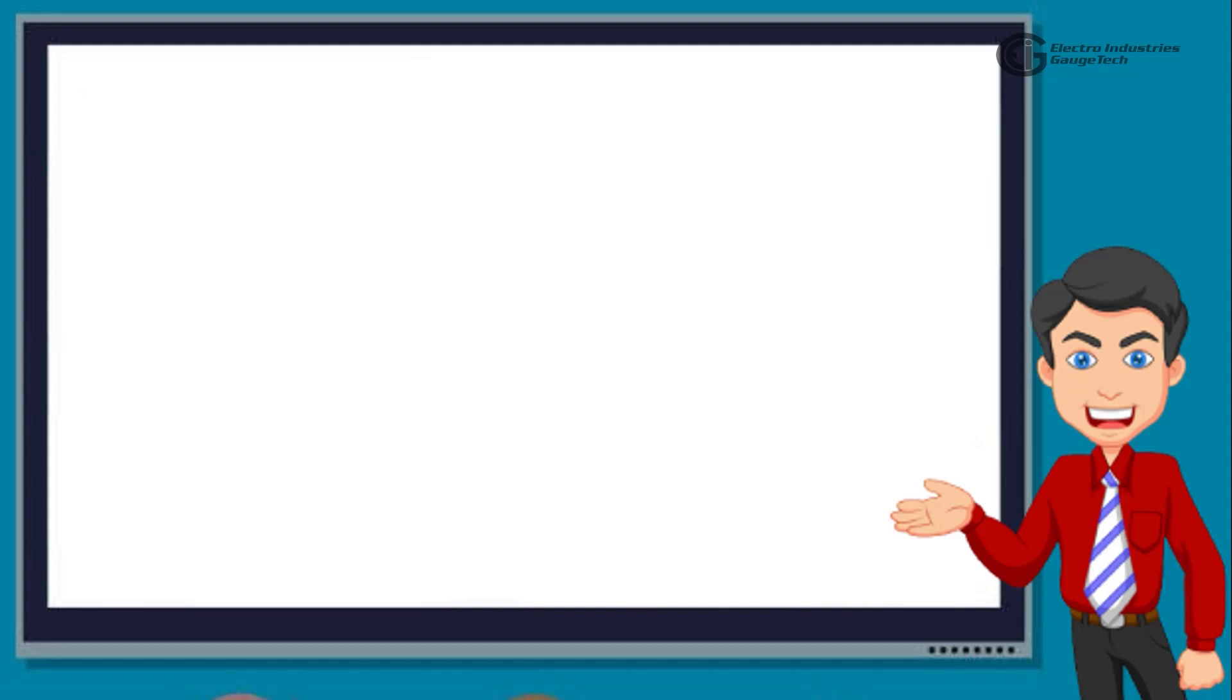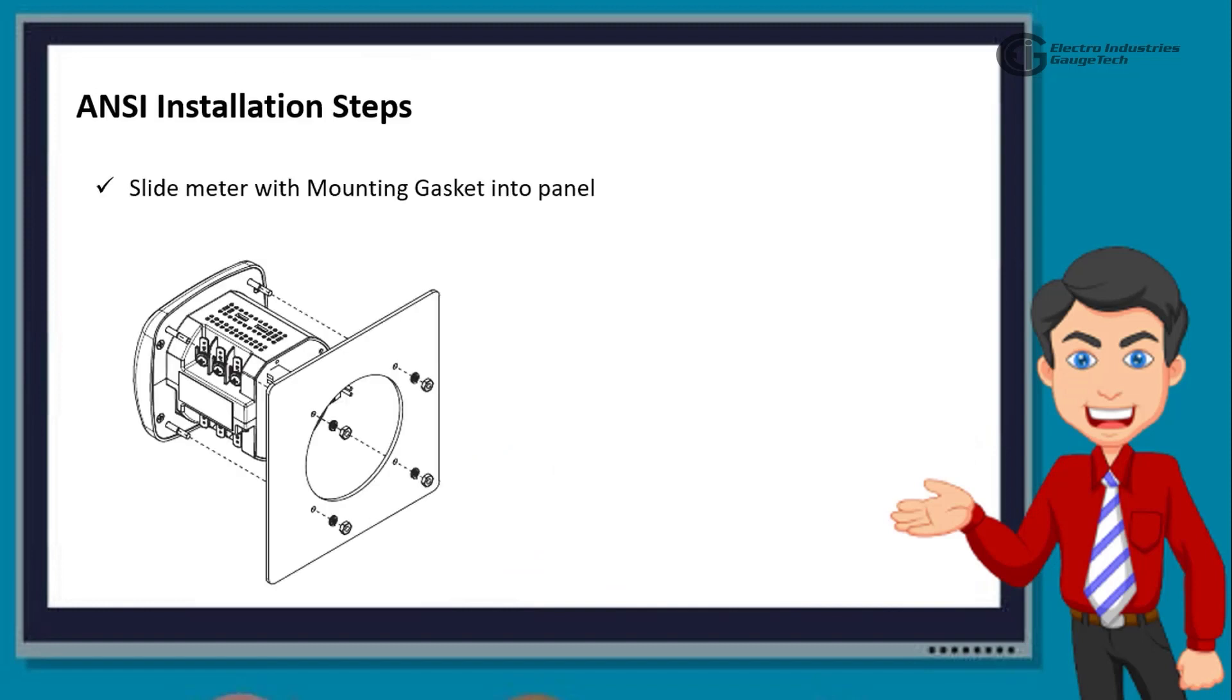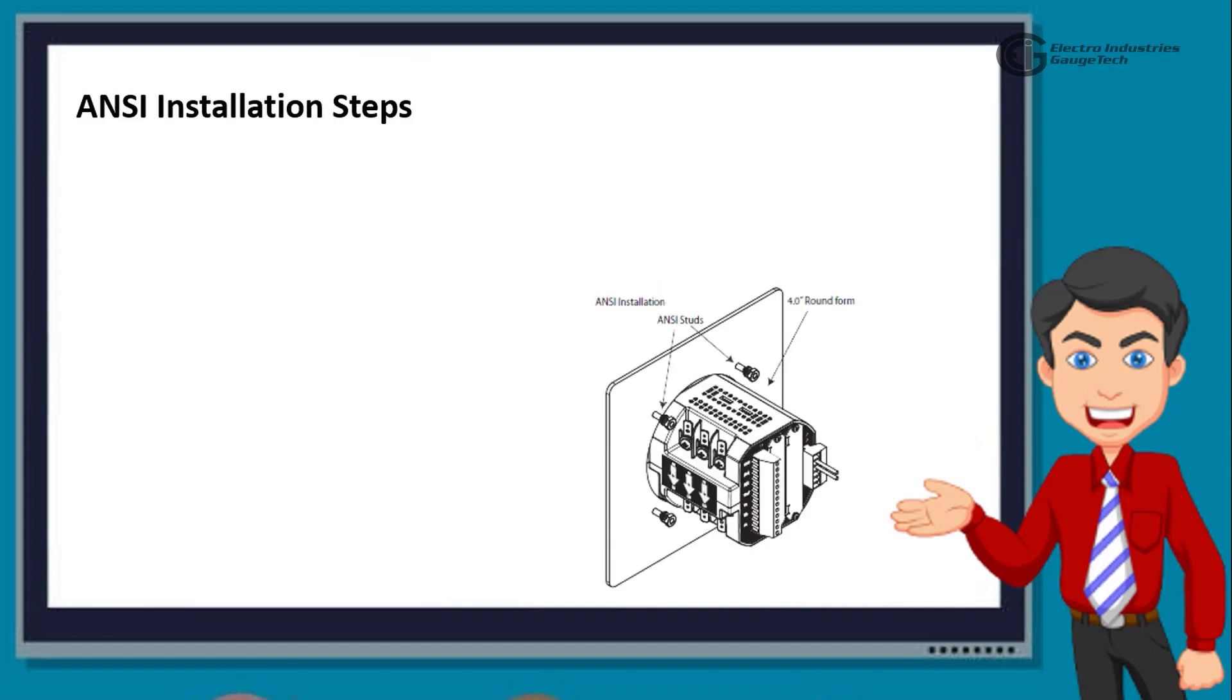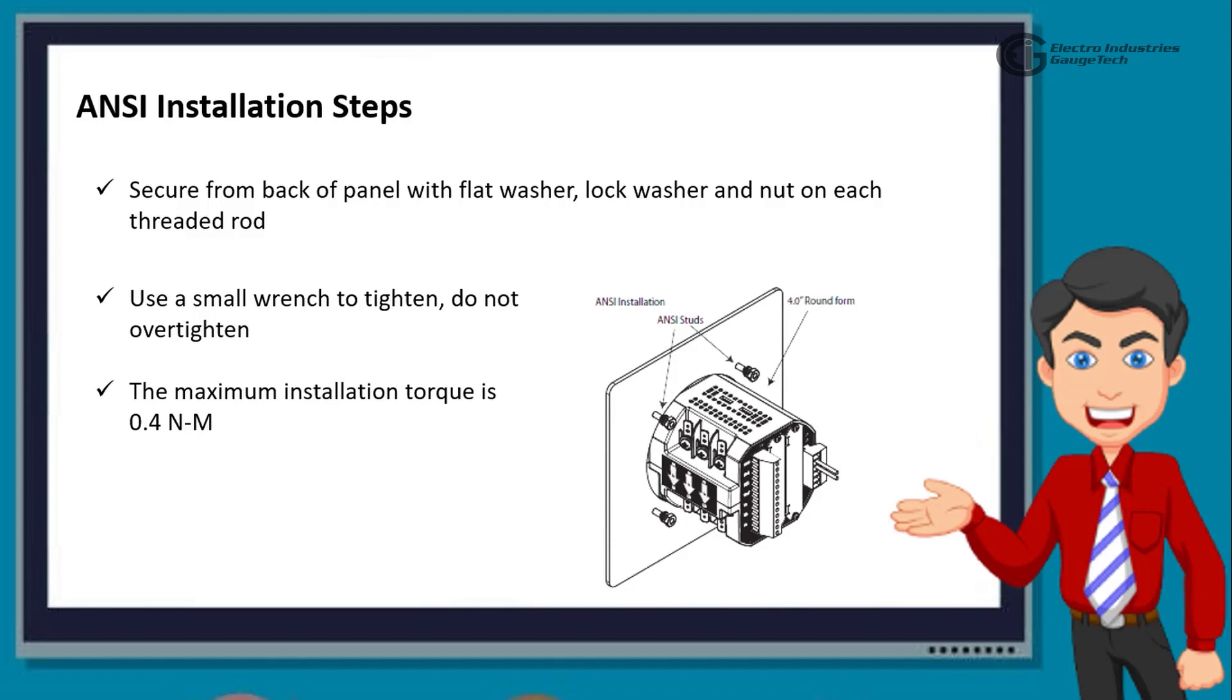Next, we look at the ANSI installation steps. First one is slide meter with mounting gasket into panel. Then, secure from back of panel with flat washer, lock washer, and nut on each threaded rod. Use a small wrench to tighten. Do not over-tighten. The maximum installation torque is 0.4 Newton meter.